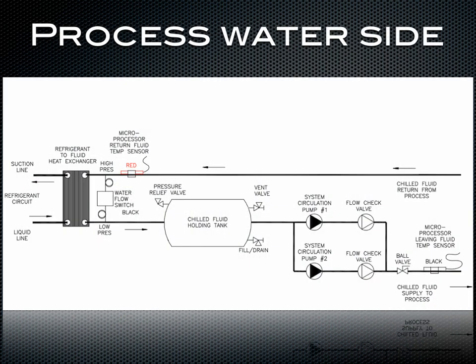Now let's go over that drawing and get a really good visual on the process water side of a chiller. A piece of equipment generates heat, and what a chiller does is remove that heat. Our piece of equipment is going to generate heat and the process fluid comes in around 55 degrees Fahrenheit to the chiller evaporator — which is this piece right here. The evaporator, sometimes called a chiller barrel, is where the process water side and the refrigerant side meet and the heat is transferred. The fluid from the process never physically touches the refrigerant fluid.